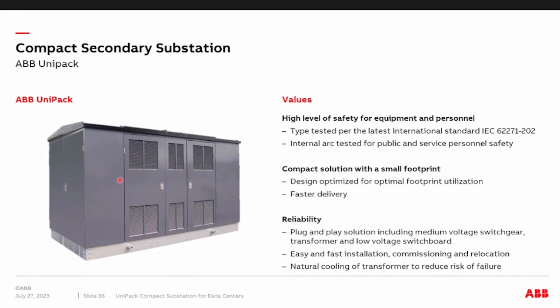This is also tested in accordance with IEC standards. This is type tested as per the latest international standard, IEC 62271-202. This is internally arc tested for public and service personnel safety, so you can actually house it outside the building where people can pass. Of course, this will be lockable to avoid unauthorized access.